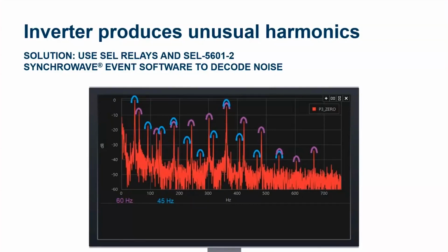We cleaned it up. The blue harmonics went away. But what remains, and we're here shown both together, are the purple. Now, these we've decoded. These are components that come specifically from the generator, not from the engine, and they are from the generator winding. Inconsistencies in pole pitch, in winding construction, in magnetic construction have created on this small generator a rich set of harmonics that need to be dealt with. Now, how do you even know they exist? You have to use a device like an SEL relay, and then software like SynchroWave Event to decode it.